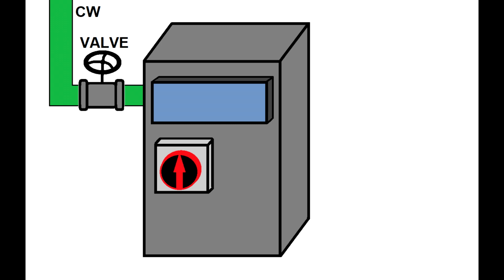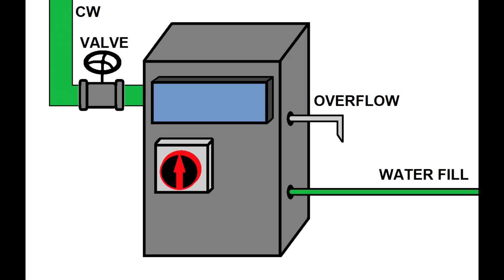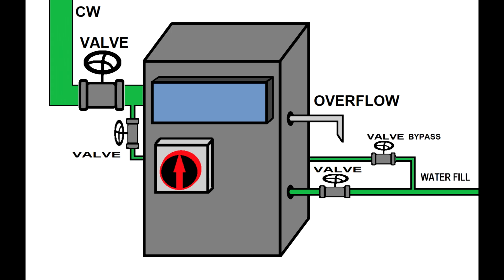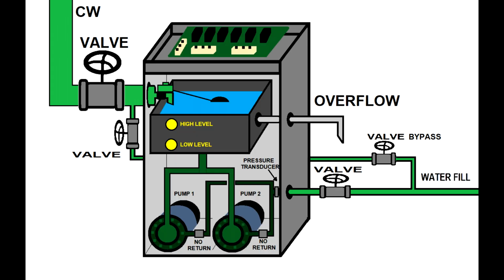Now let's talk about the pressurization unit. What are they and where do we use them? A pressurization unit looks like a metal box, but this metal box has a lot of parts inside. It is connected to the main water supply, and you'll obviously use an isolation valve in case you want to remove it or repair it. Also, the pressurization unit has an overflow, and I'll explain to you why. The water fill pipe will be connected to the pressurization unit, and it will have a valve in case you want to remove it. Also, the pressurization unit has a bypass. In case it becomes faulty, you have to fill the system manually.